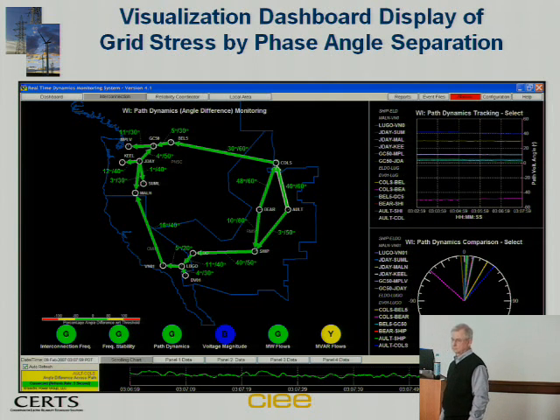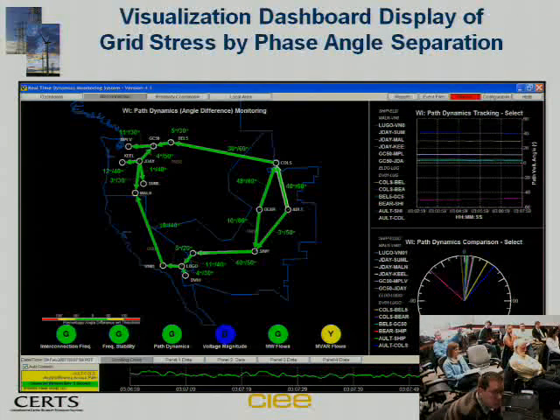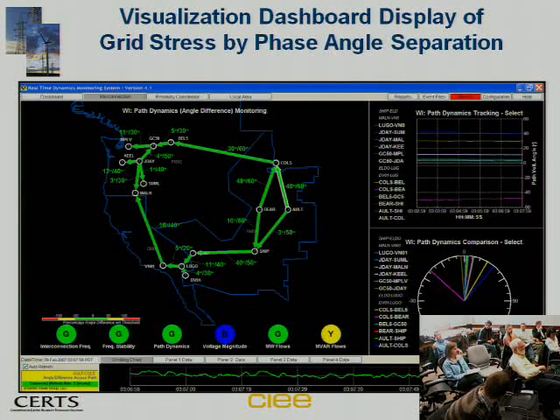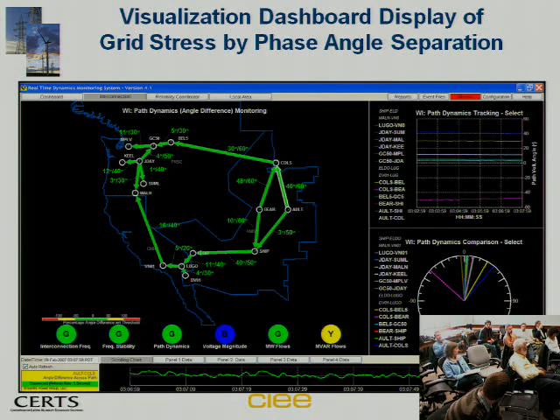What you have to do is control generators and actually increase or decrease the excitation controls on the generators, having a certain generator put out more power, increasing the phase angle at its bus to send power down to a load somewhere else. It's very tricky to do, but the operators can do it, if you have to do it completely manually.